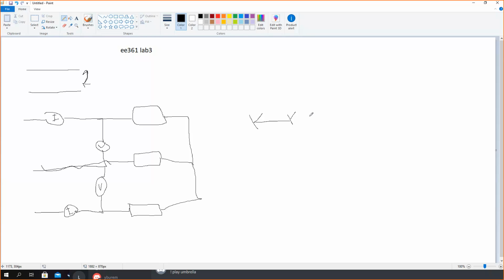But in this case, the third harmonic problem may be solved by a delta-Y connection. Also, in a balanced system, when all currents and power factors are the same, the phasor sum is 0. Because of that, there is no need to connect neutrals.